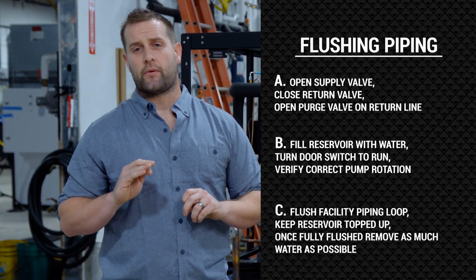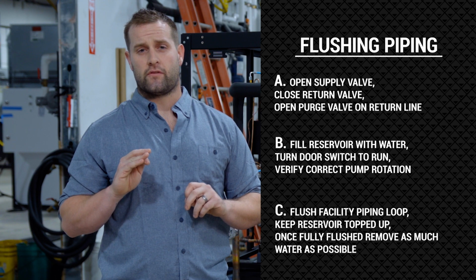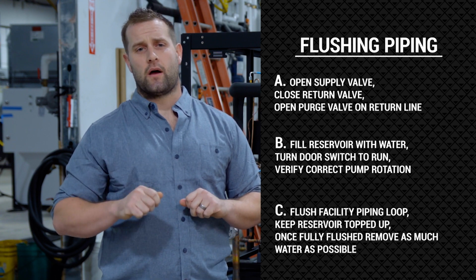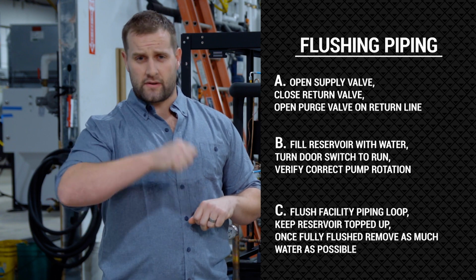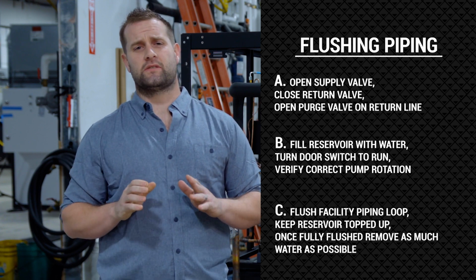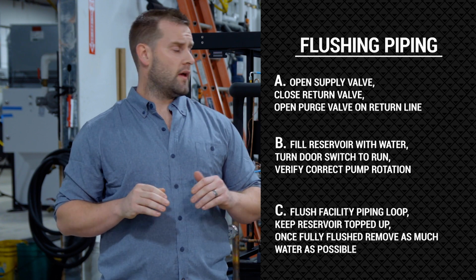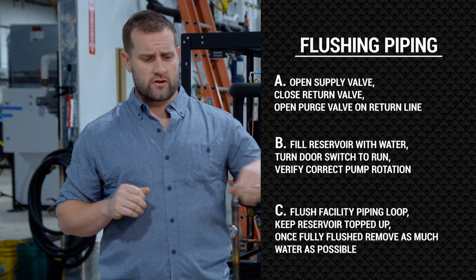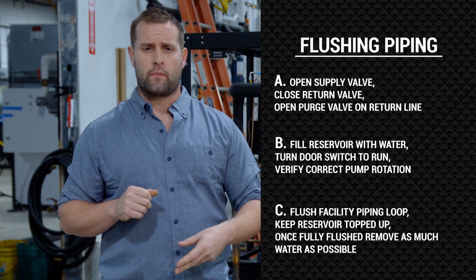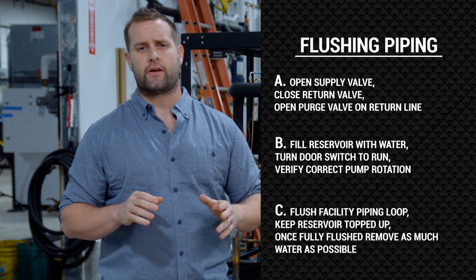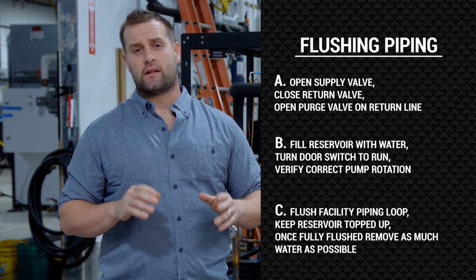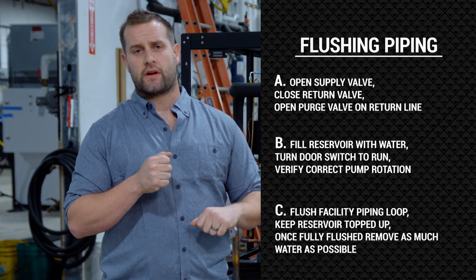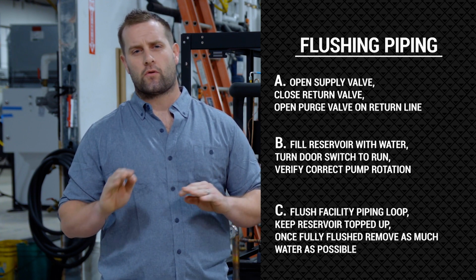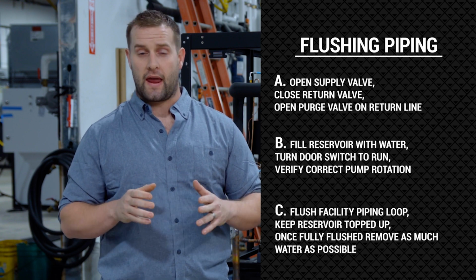This is a very good opportunity to check the rotation of your pump. From the back side of the pump, you're going to want a clockwise rotation. If you have any questions about that, you can call us. Once you've flushed, look at all the water coming out your Y strainer and make sure it's clean and clear. Once that is clean and clear, you can button up that Y strainer and stop filling your reservoir, and get all the water out that you can before buttoning up your Y strainer.